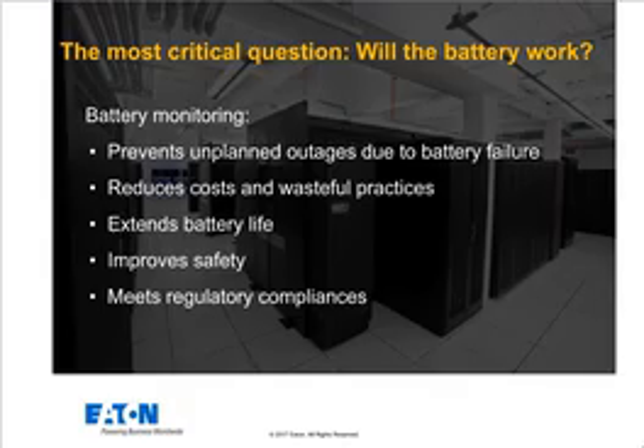Okay, we're going to change topics a little bit to the battery, because regardless of all this generator interface discussion, the battery has to be there and work properly in order to bridge the gap between the loss of utility power and the UPS or the generator startup. So this brings to mind the topic of external battery monitoring. Most, if not all, UPSs will monitor the battery string voltage and let you know if it gets too high or too low. Some of them will actually perform a battery test once every few weeks or once a month. But again, that's not quite as granular as some clients like to see.